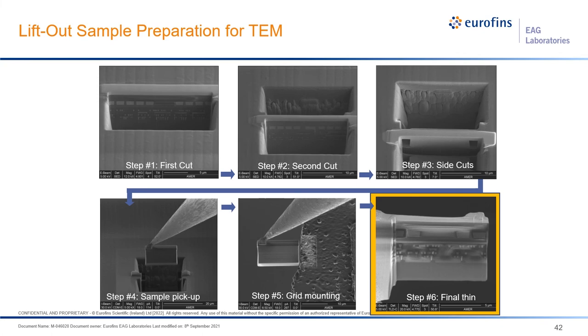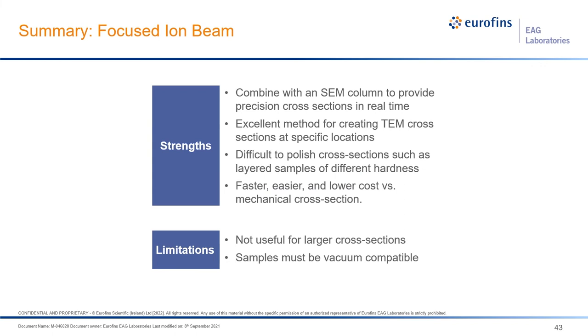In summary, focused ion beam combines all the benefits of an SEM column and allows precision cross-sections in real time. It's an excellent method for creating TEM cross-sections at very precise locations and for producing polished cross-sections on difficult samples — ones with different hardnesses that smear or are otherwise unable to be processed mechanically. It's faster, easier, and cheaper than mechanical cross-section.